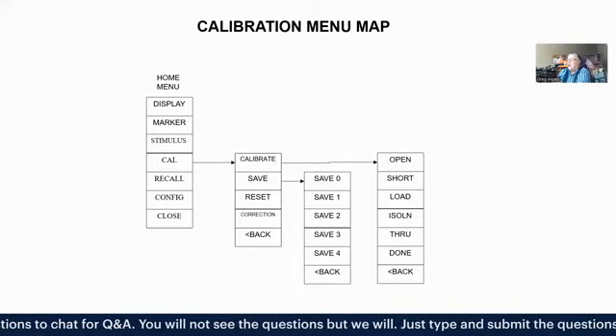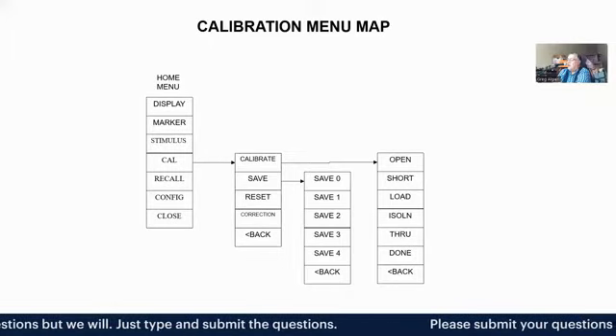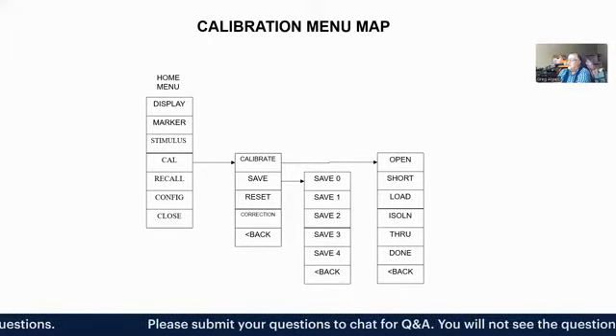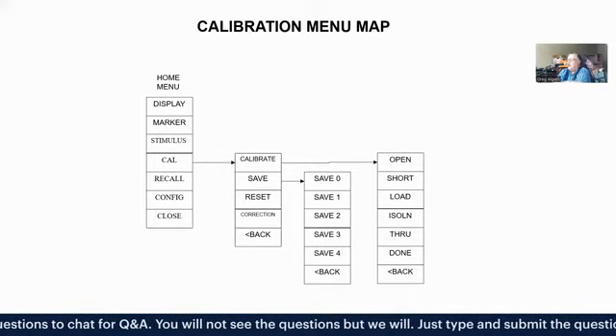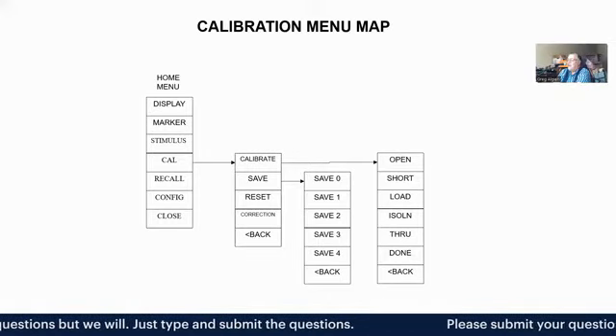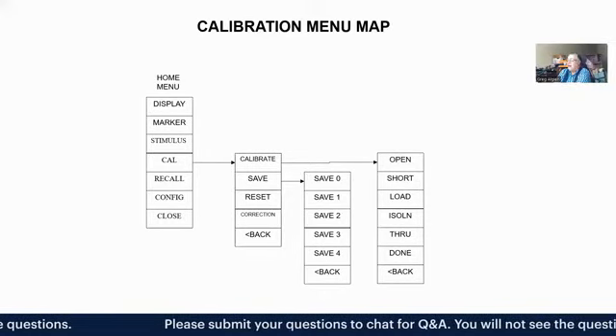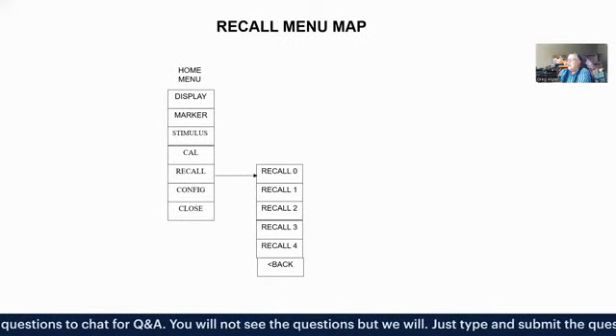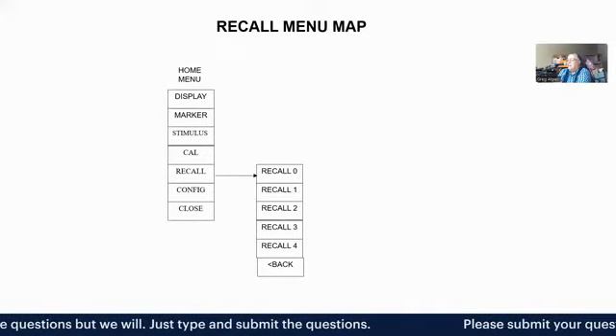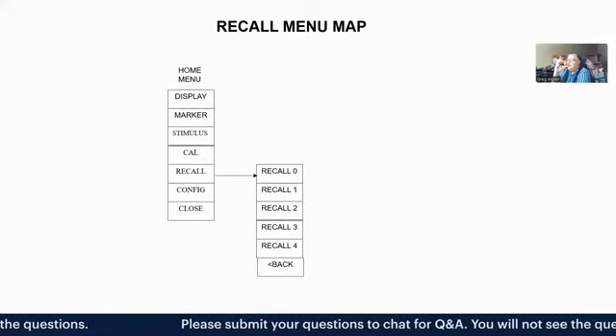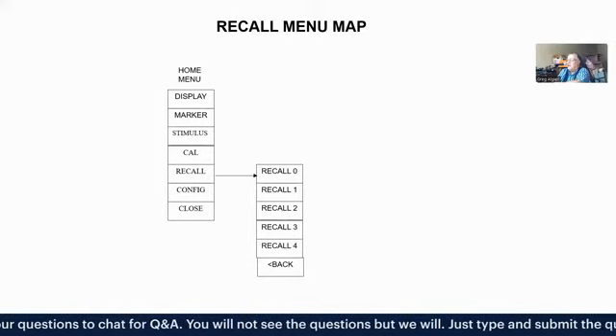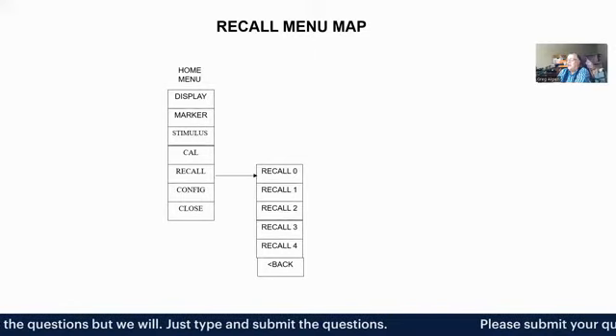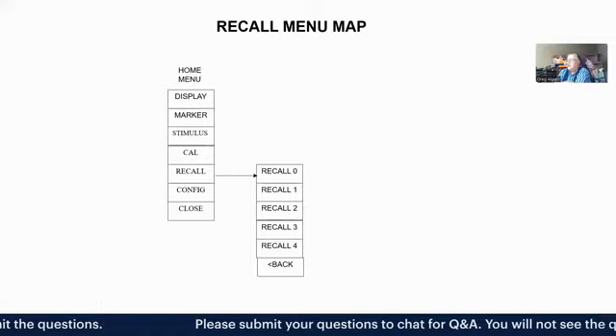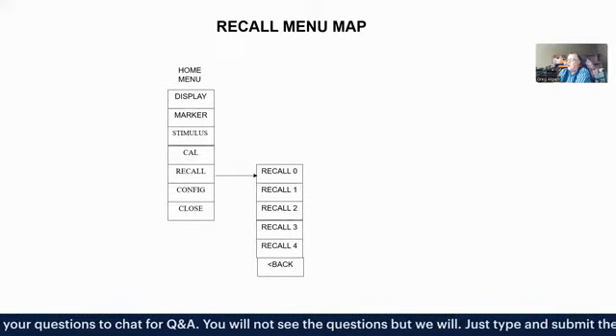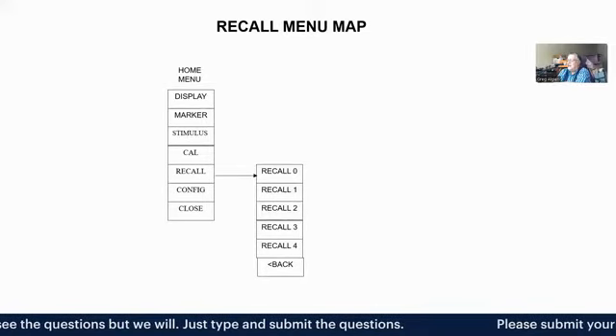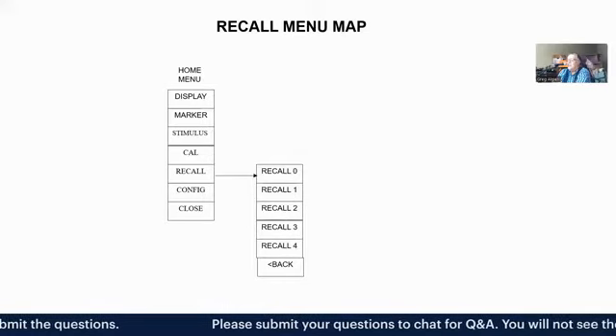When you do the calibration, it walks you through putting the open, short, load, isolation and then doing the through. And then when you get done with that, you hit done, and then it gives you the option to save that calibration in one of 5 different spots. If you have a particular setup that you want to use quite often, you can set the Nano VNA up for that particular thing, and then you can save that setup into a memory location. Then if you want to go back to it, you can just hit this recall button, recall the location where you saved it, and all those things that you set up the first time will come back into the Nano VNA.